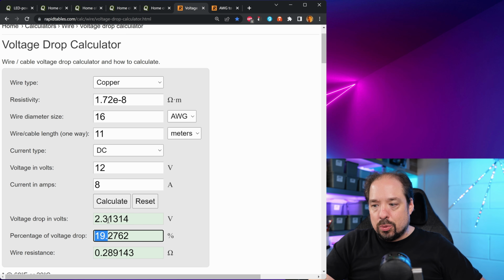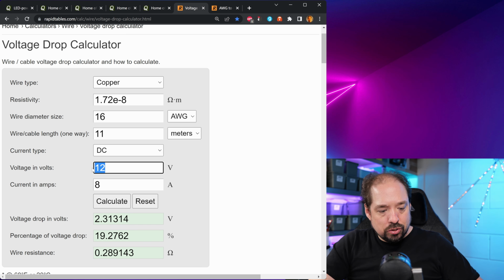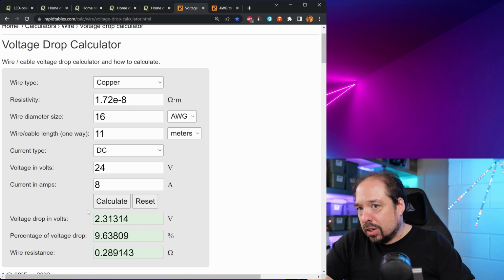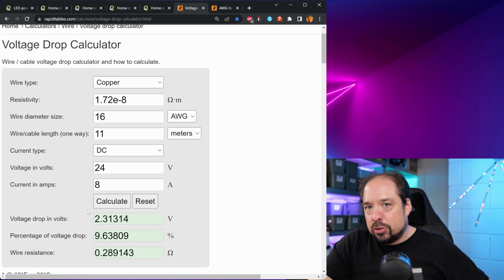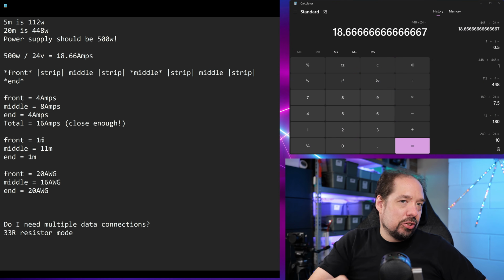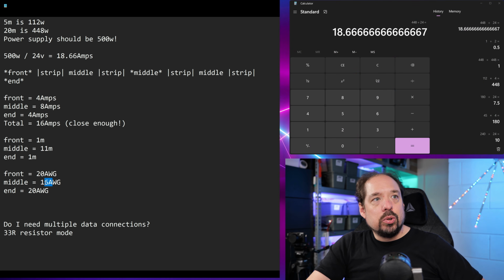Right? Because now we're dropping 2.3 volt, which indeed makes sense, which is below the 2.4 for 24 volt, but not below 1.2. So we can copy some of it, but we still have to do the calculations. So we can use thinner cable here for a middle injection.